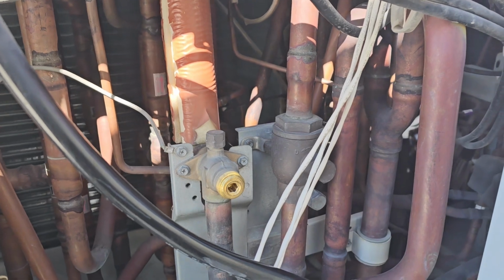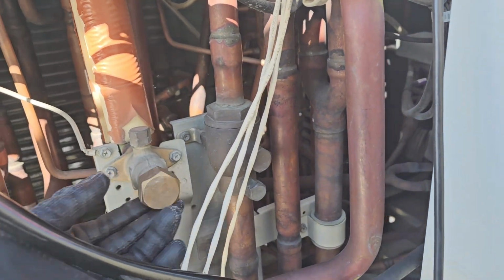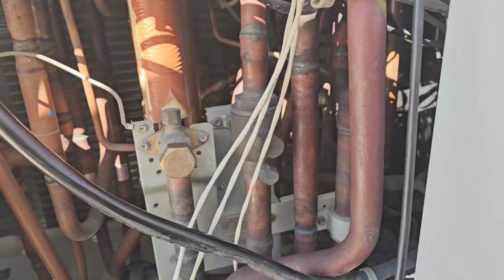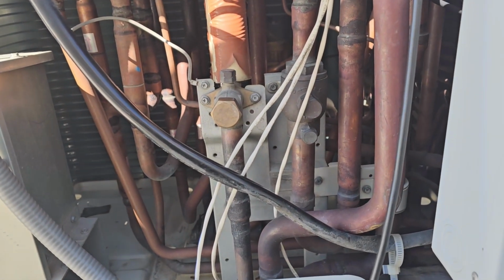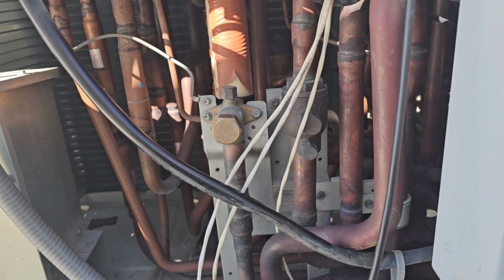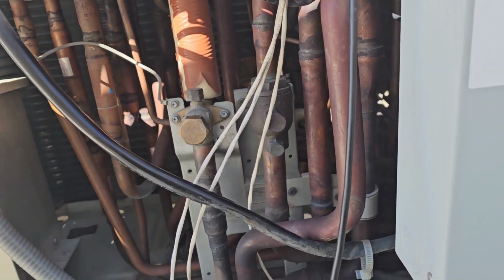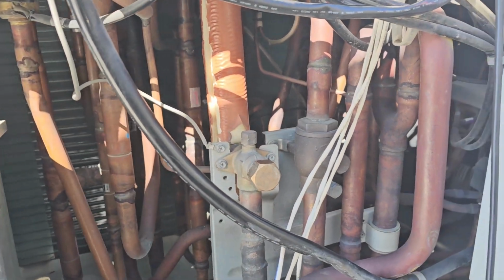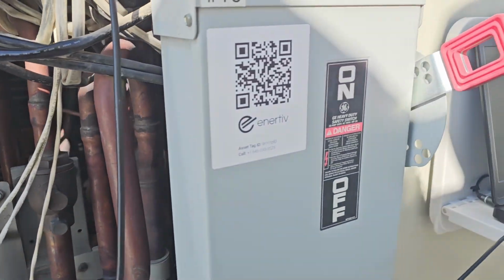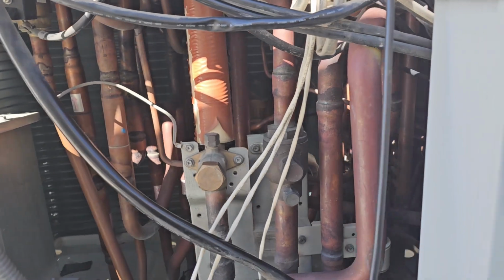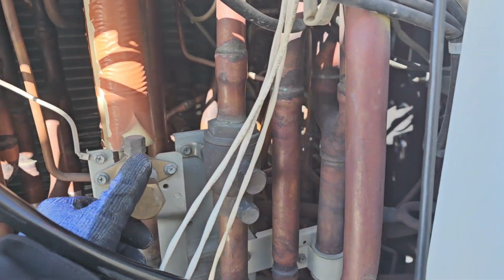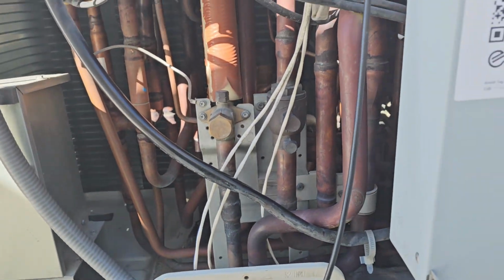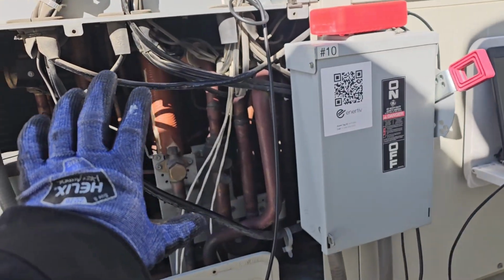Now, I don't understand why, but it's because our ball valves on our outdoor unit were closed. Yet the unit would still run, and it would only occasionally trip on high head. It only tripped like 3 times, but it would run for 15-20 minutes. So somebody came up here and shut this ball valve off. Both of them. So this entire unit was isolated.